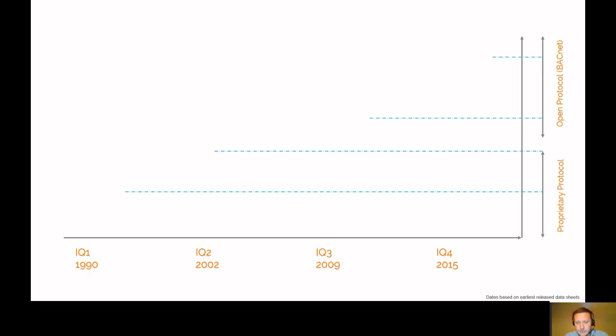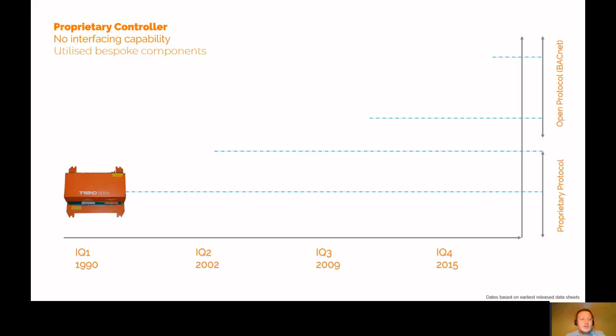Going back to trend, this slide perhaps isn't obvious until the end. Looking at the dates things came out: the IQ1 came out around 1990, the earliest data sheet I could find. Twelve years later we had IQ2s, so twelve years between those two families. Seven years after that we had the IQ3, which was the first time we came across industry standard IT components. The benefit is they cost a lot less, they're not bespoke, and it means anyone can create the chipsets from standard industry parts. They also added some BACnet capability at this point, which was great.